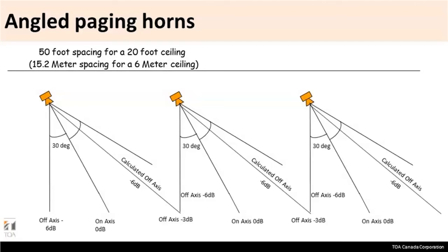So you have to make sure that you place the speakers evenly, and the angle of the speaker shouldn't be firing too high, otherwise you're just firing it off straight. At the same time, you're not firing it too low, so that only the person standing just below the speaker is able to hear the announcement, and when you start moving away from the axis you hear nothing. You don't want that. You want to make sure that when a person is walking in the aisles, the audio announcement is very audible. So in usual cases, it's roughly 45 to 50 feet spacing of the speakers. Anywhere you walk from left to right, you'll be able to hear the intelligible announcement, and the variance will be only around 3 dB.